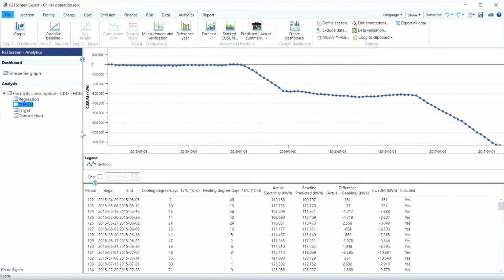Whoa, okay. So what we've done is say that there is this regression equation that's holding very well from May until, what can that be? Until January? So there's heating and cooling effectively until January. And then there's a large, constant reduction in energy.